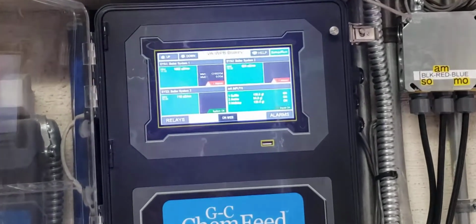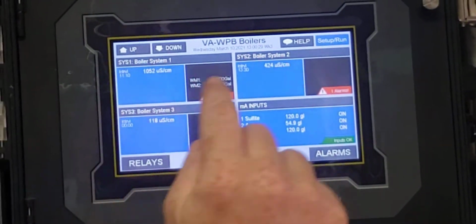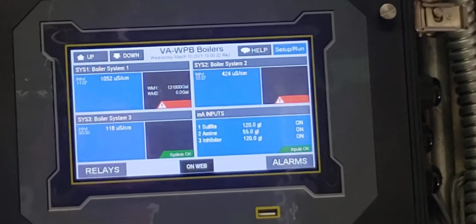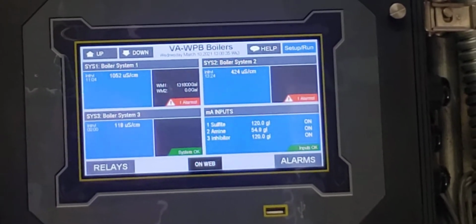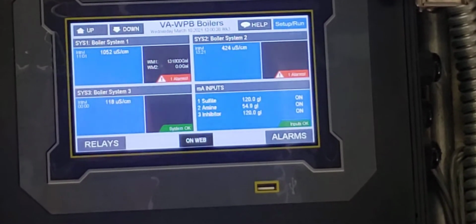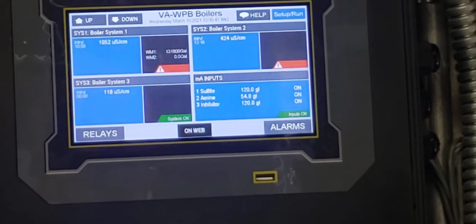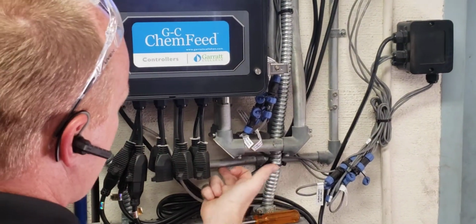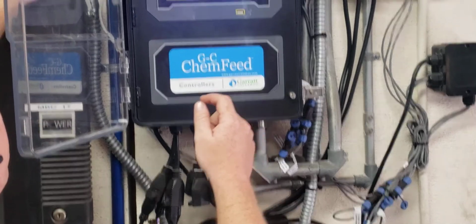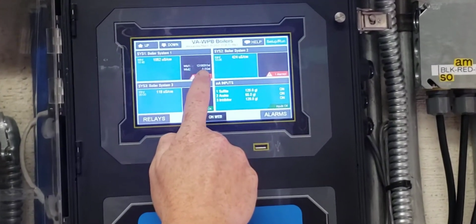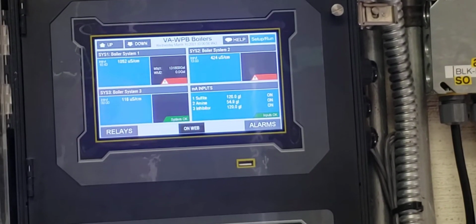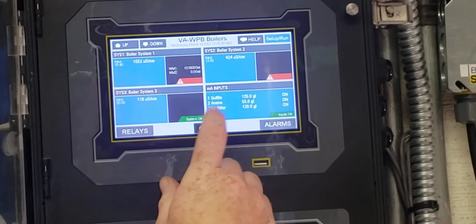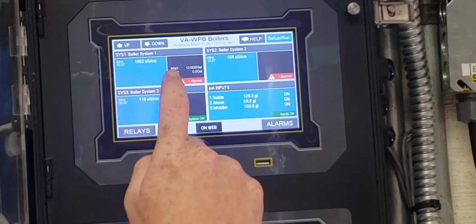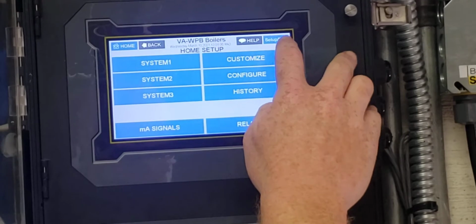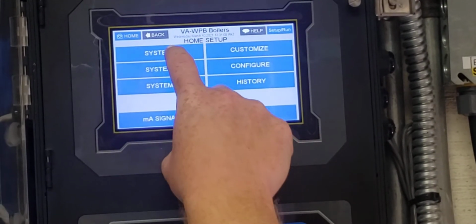All right, so let's first go over this. Each conductivity reading is taken from a probe on top of each boiler. I believe this is the conduit coming in for that, or that's the water meter. This is the blowdown power, this is the conduit for the conductivity probes, this is your water meter coming into the controller. This also tells you how many gallons since it's been reset from the water meter that's behind us, behind the soffit.